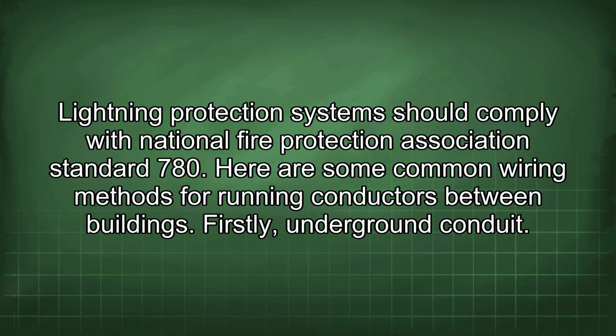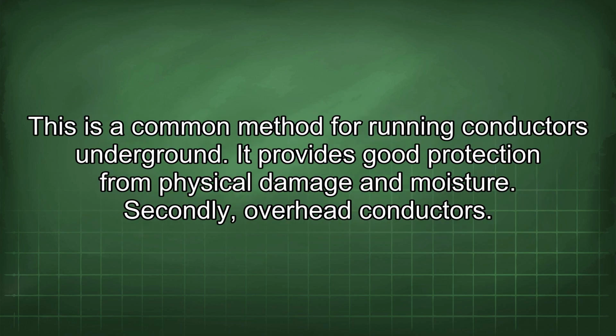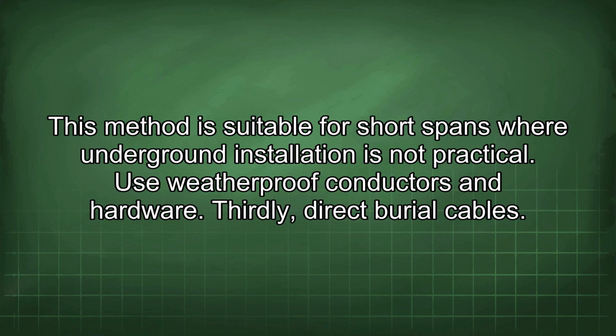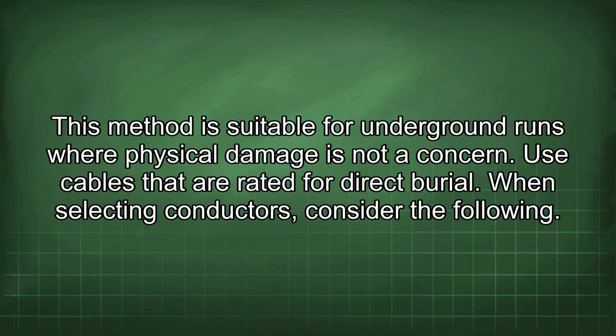Here are some common wiring methods for running conductors between buildings. Firstly, underground conduit. This is a common method for running conductors underground. It provides good protection from physical damage and moisture. Secondly, overhead conductors. This method is suitable for short spans where underground installation is not practical. Use weatherproof conductors and hardware. Thirdly, direct burial cables. This method is suitable for underground runs where physical damage is not a concern. Use cables that are rated for direct burial.